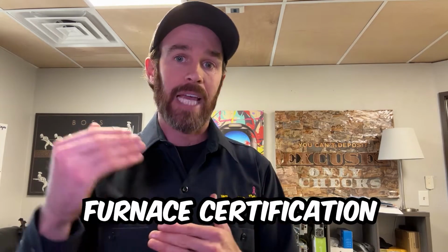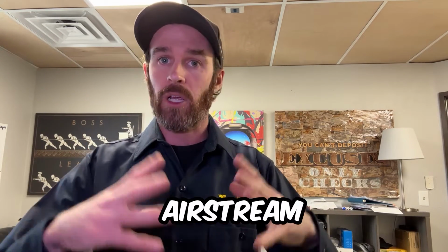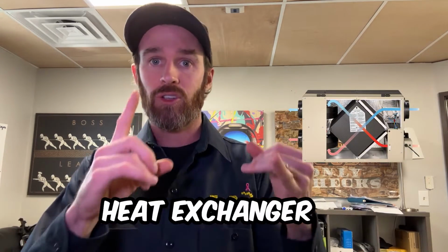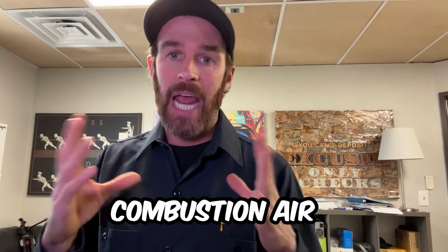So that's a nutshell version of what carbon monoxide is in the context of this video as it relates to furnaces and boilers. And one of the things that most HVAC companies will do when they are doing a tune-up or a furnace certification is check for CO in the airstream or in the mechanical room. And this is to determine whether or not you have a compromise in your heat exchanger, your exhaust piping, or whether or not you have poor drafting and not enough combustion air, for example. Now, oftentimes we come across systems that have levels of CO either coming out of the heat exchanger from a boiler or a furnace, and when it is entering the airstream in the home or leaking from the cabinet, for example, in this case of a cast iron boiler, that creates a potentially hazardous situation.